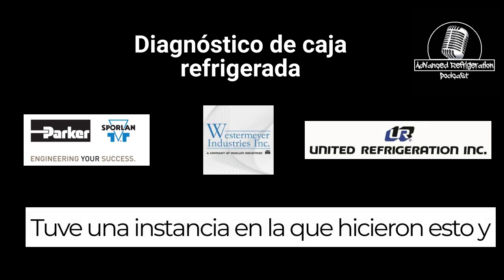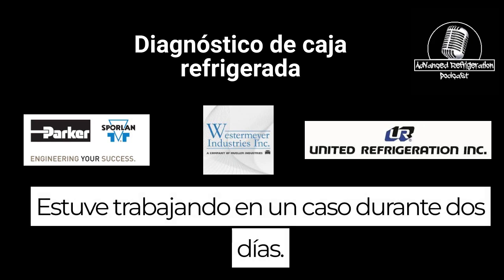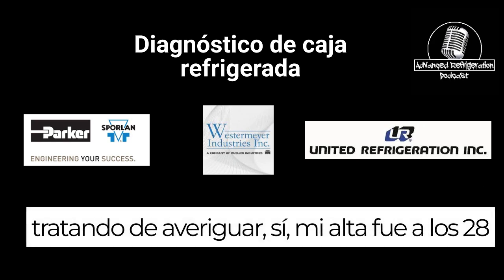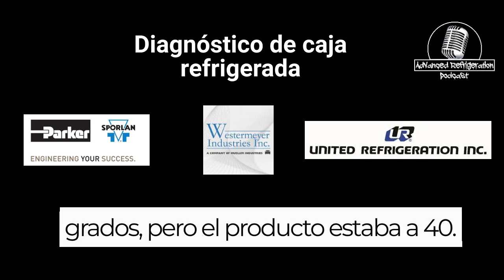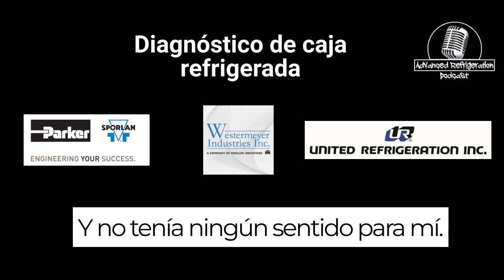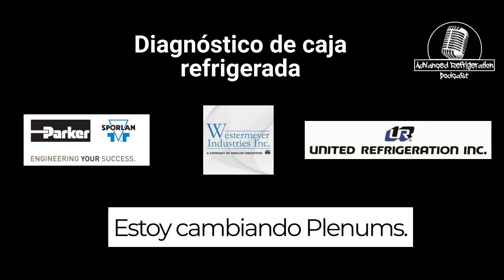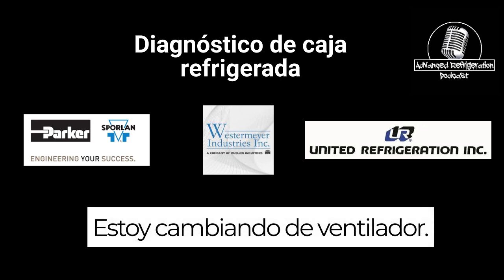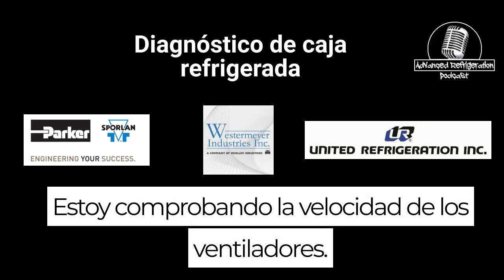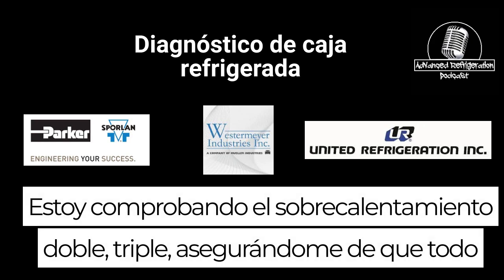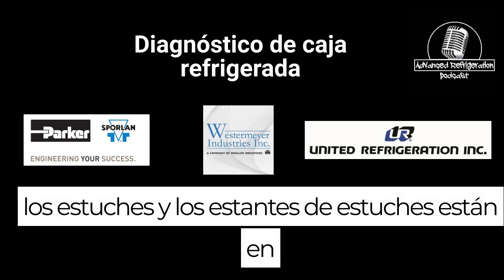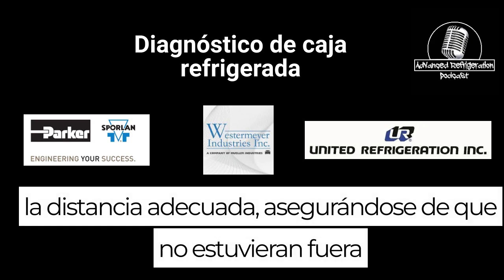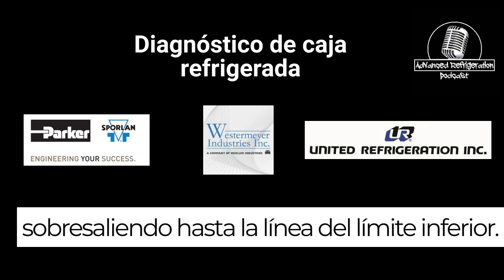I had an instance where they had this done, and I had been working on a case for 2 days trying to figure out why my discharge was at 28 degrees, but the product was at 40, and it didn't make any sense to me. I'm switching around plenums. I'm switching around fans. I'm checking speed on fans. I'm double, triple checking superheat, making sure all the cases and the case shelves are at the proper distance, making sure they weren't out and protruding into the load limit line.